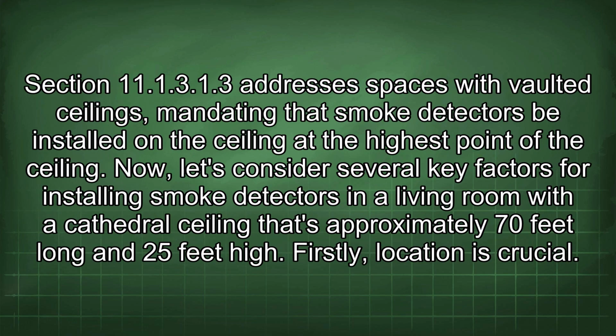Section 11.1.3.1.3 addresses spaces with vaulted ceilings, mandating that smoke detectors be installed on the ceiling at the highest point of the ceiling. Now, let's consider several key factors for installing smoke detectors in a living room with a cathedral ceiling that's approximately 70 feet long and 25 feet high.